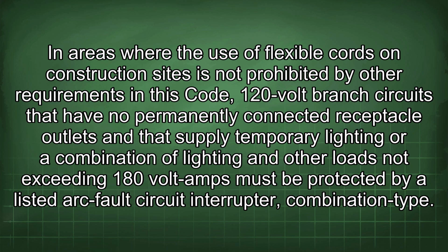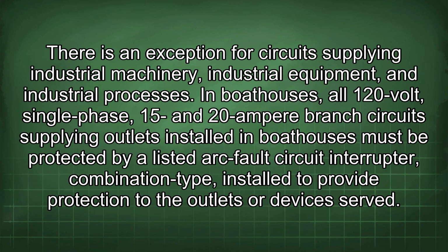In areas where the use of flexible cords on construction sites is not prohibited by other requirements in this code, 120-volt branch circuits that have no permanently connected receptacle outlets and that supply temporary lighting or a combination of lighting and other loads not exceeding 180 volt-amperes must be protected by a listed arc fault circuit interrupter combination type. There is an exception for circuits supplying industrial machinery, industrial equipment, and industrial processes.